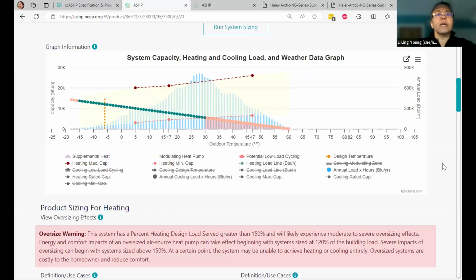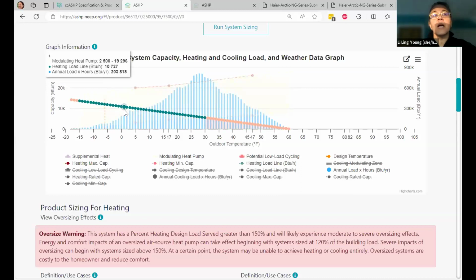And then, of course, you recognize those blue bars in the back, we already talked about those. So what this is showing is that the load of the building is within the range of what the heat pump can provide for this long stretch here. Starting right here, the load of the building can be met by the heat pump capacity, and it just modulates in order to meet that load. So it's not at high speed all the time, but it's higher than low speed.